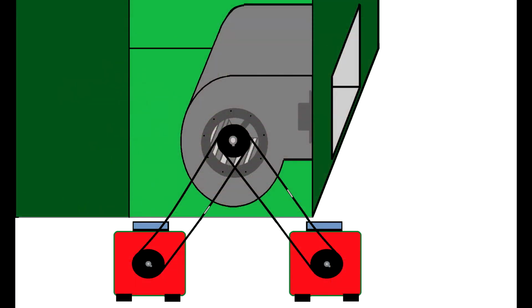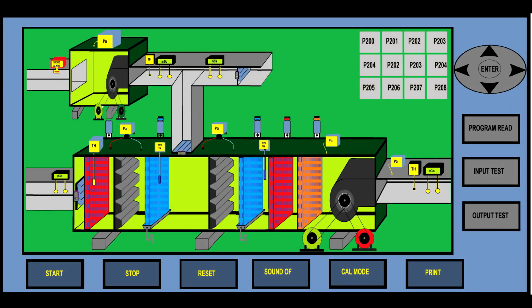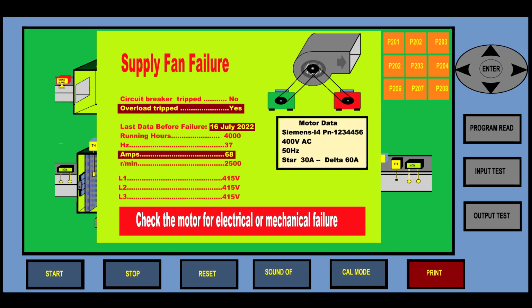This type of ventilation is the one we use the most. Again, this fan doesn't overheat the supply air chamber, but there are pros and cons. You can have a broken belt, you can have a mechanical failure which will affect the entire system. One bearing through the belt will stop the entire system. If you have only a simple electrical failure, the motor will switch from one to another, then the rooms will tell you it's been a glitch in the system. So you have to reset the rooms. So resetting the rooms means you acknowledge the failure.